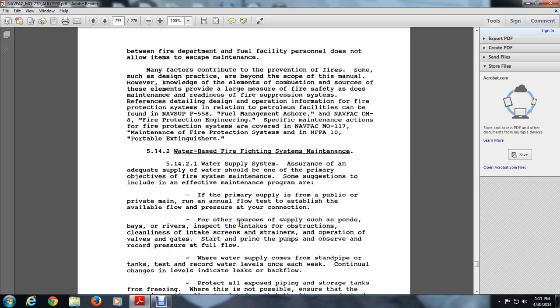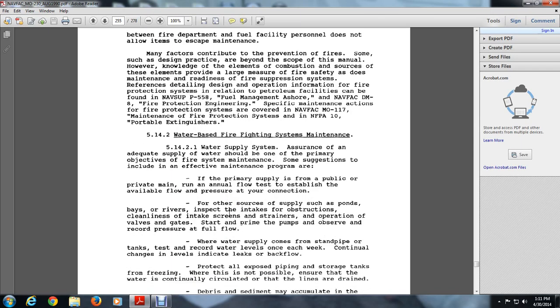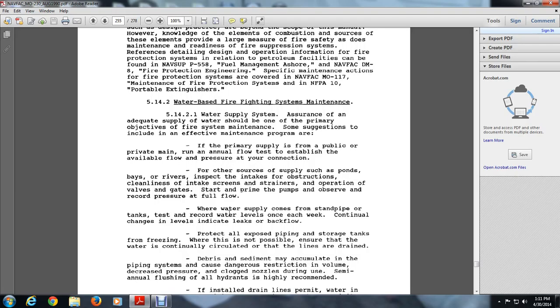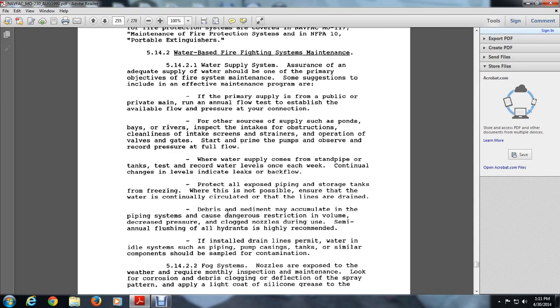When water supplies comply with the standpipe, test the tank and record levels at each test. Continual changes in the level indicate leaks and backflows. Protect all exposed piping and storage tanks from freezing weather where possible, ensuring that the water is continually circulated or that the line is drained. Debris and sediment may accumulate in the piping and systems and can dangerously restrict the volume, damaging pressure from a clogged nozzle during use. Semi-annual flushing of all hydrants is highly recommended. If installed, drain lines permit, water in idle systems such as piping, pump casing, and tanks and similar components shall be sampled for contamination.